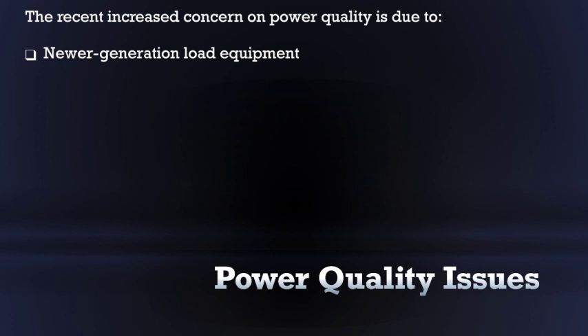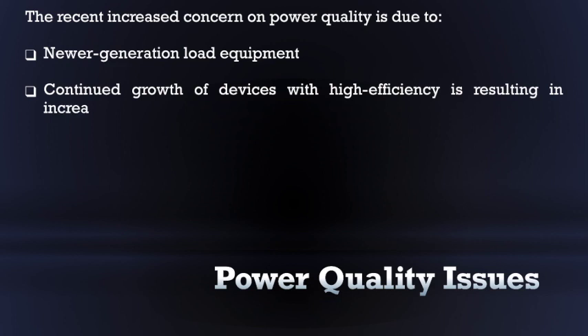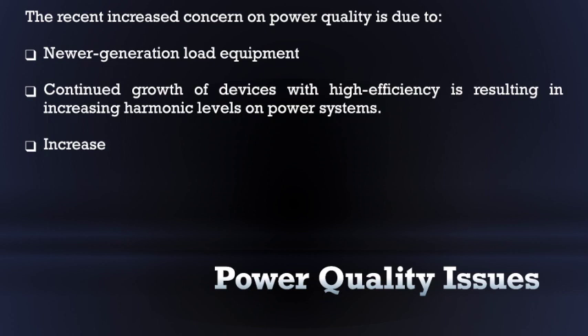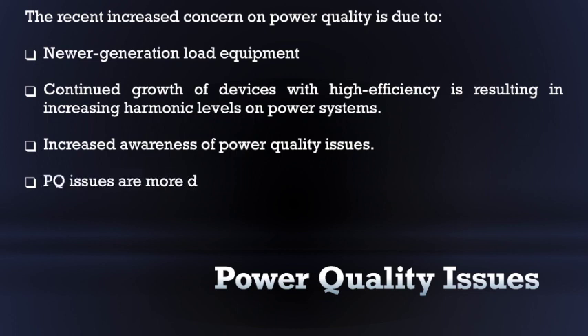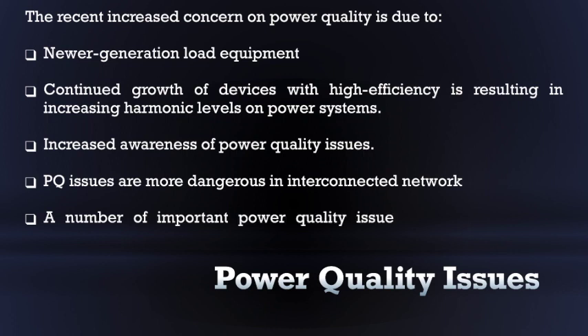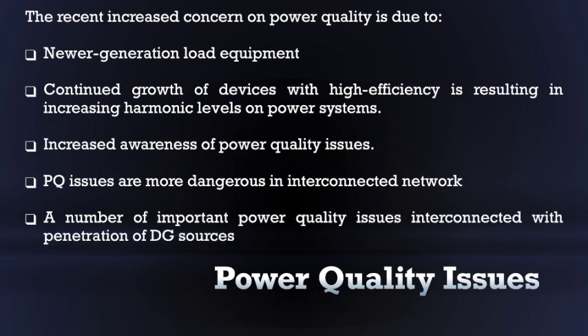The second point is that the increasing importance on overall power system efficiency has resulted in continuous growth of devices with high efficiency. Devices like adjustable speed motor drives and shunt capacitors for power factor correction are being increasingly used to reduce the losses and to improve the efficiency. This growth is resulting in increased harmonic levels in the power system. Also, nowadays the end users, that means the consumers, have an increased awareness on power quality. They are challenging the utilities to improve the quality of power delivery.